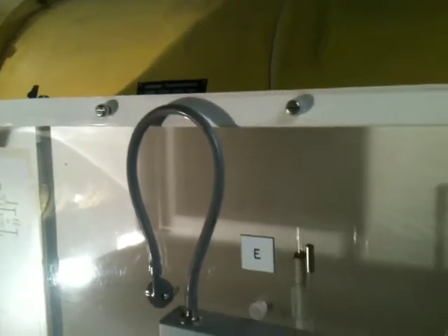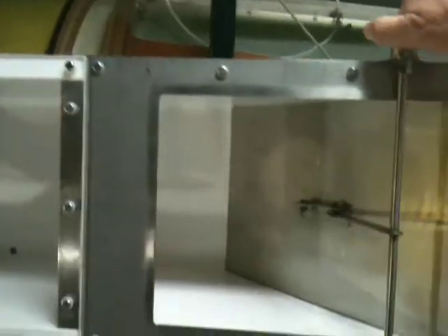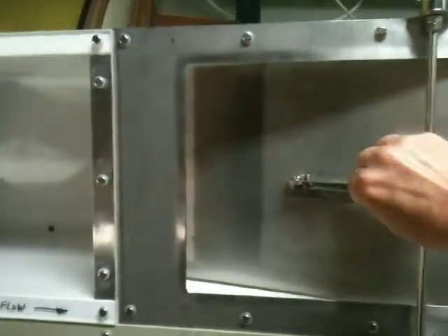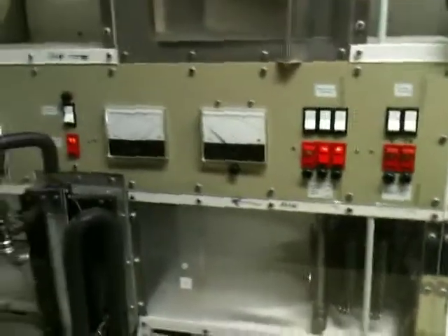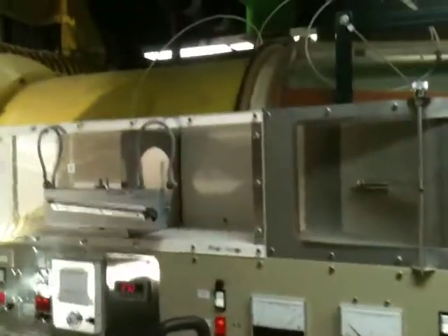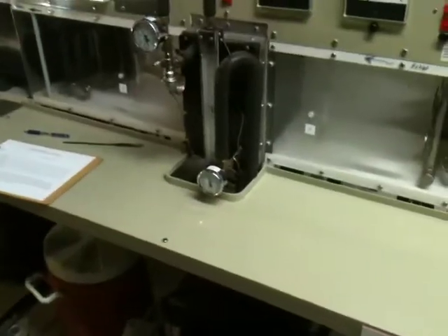So at station E, we saw that the wet bulb and the dry bulb were fairly high, reflecting that added heat. Okay, so for the final exercise, we are going to close the damper here. It doesn't close all the way, but we're going to close it a fair amount. Okay, so now a lot of the air is going to recirculate, and since we're injecting moisture into it, we're going to build up quite a bit of humidity, and we'll probably get some condensation out of the cooling unit down below. We'll take a look in a minute.